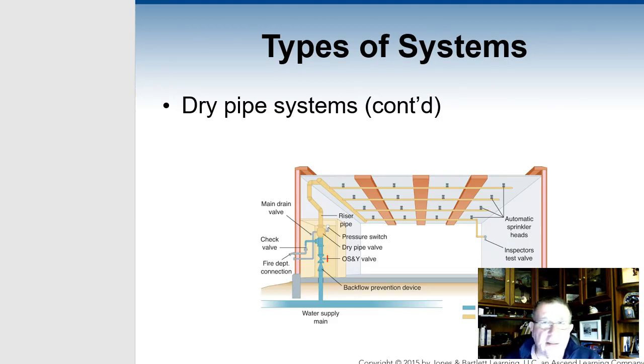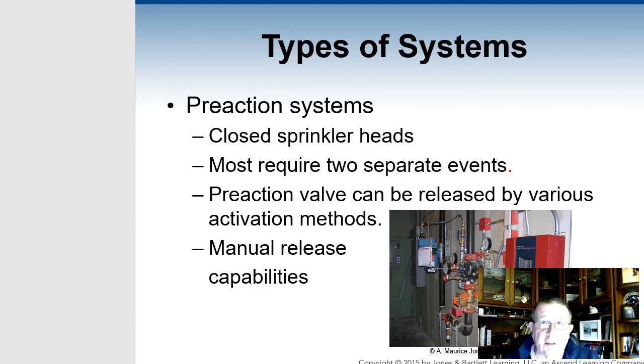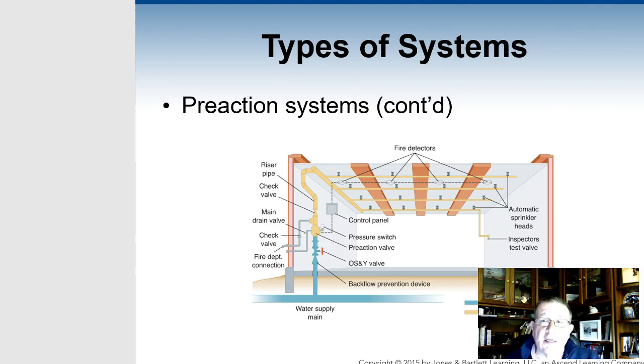The grid is laid out the same, but what you come into is how the fire department connection, OS&Y valve, and the pressure system and the connections all come together, where the water comes into the sprinkler system and how it goes in, distributed through the distribution center. So you've got all kinds of things. The biggest thing we're looking at today is some pre-action systems, where you have a sensor that goes off, or in this particular case, a smoke head goes off and the system's activated. Automatic water comes out. That's pre-action.